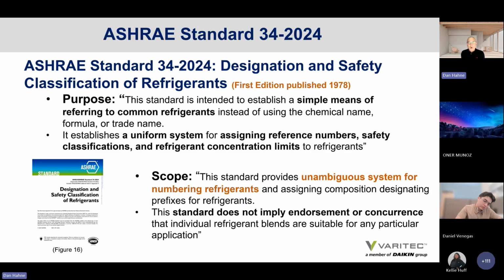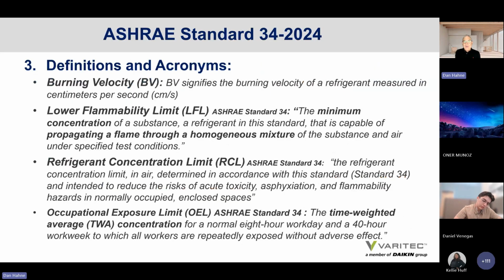First of all, Standard 34 is really created for a way of designating safety classifications of refrigerants. Its purpose is intended to establish a simple means of referring to common refrigerants, and it establishes a uniform system for assigning reference numbers, safety classification, and refrigerant concentration limits. Its scope is to provide an unambiguous system for numbering of refrigerants, and it does not imply endorsement or concurrence of any of those refrigerants. It just states each refrigerant's physical qualities.